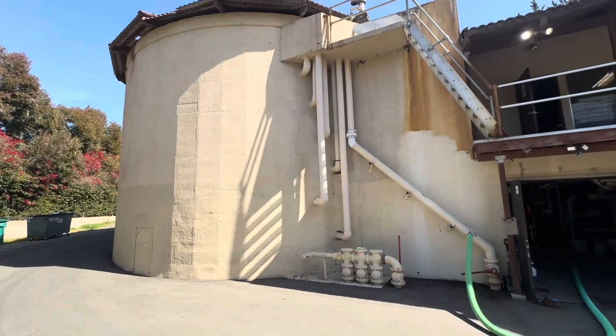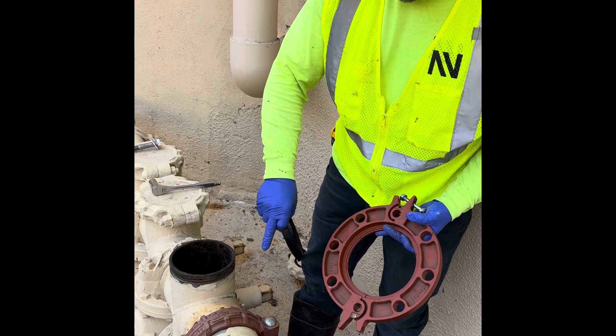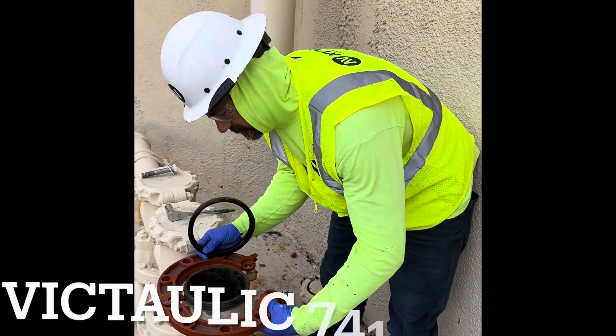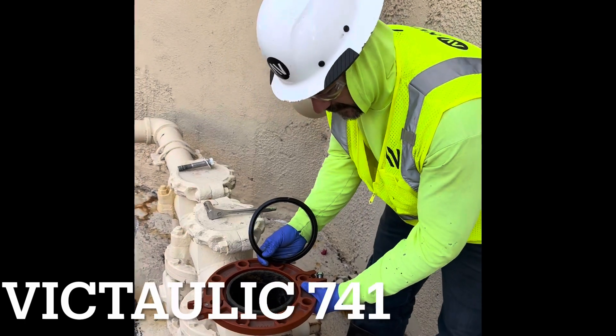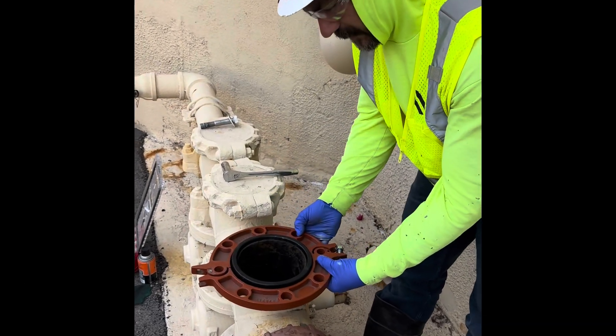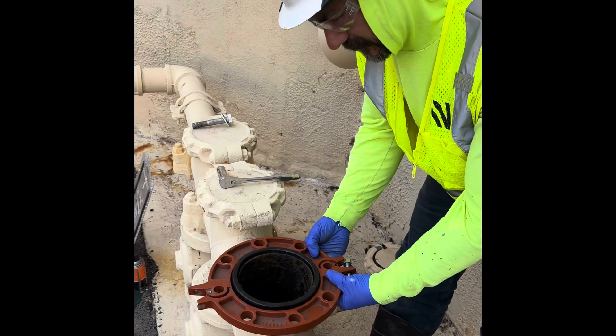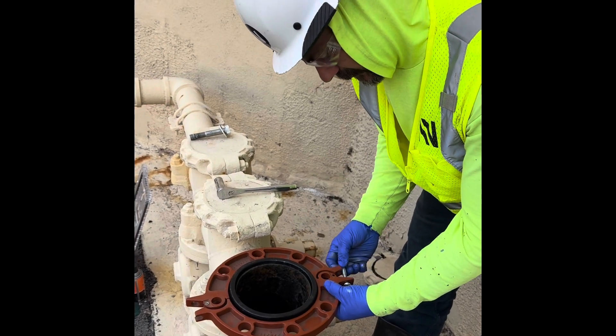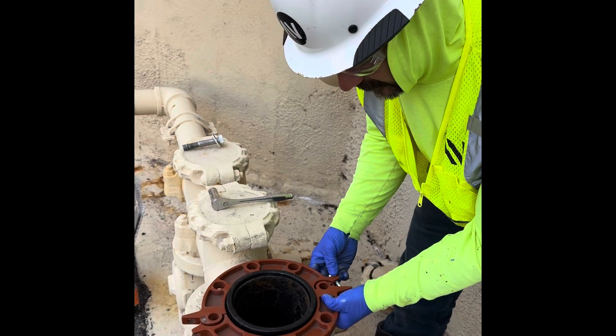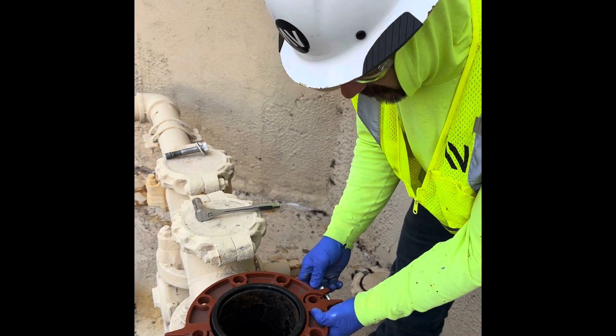Let's go on and move on to the next segment and let's repair this line. So we had a blind flange here on the manifold and what we're attaching to is a six inch flange. So this is a flange adapter, like the Victaulic 741. Basically that sticks into the groove and you have a gasket that will be on the face of the pipe there of the groove pipe. And now we can mate, ideally a steel flange to this face. There's also a stub end style if you were using a PVC 90 or a PVC flange, if you'd like to get it to mate with a full face gasket.